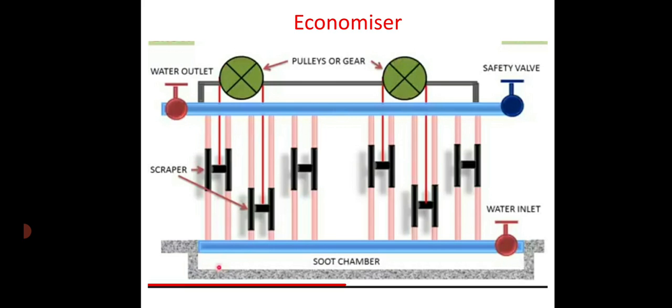The feed water is pumped into the economizer and enters the bottom pipe. It then passes to the bottom box and then into the top box through the tubes. There is a blow off cock opposite to the feed inlet to remove the mud.